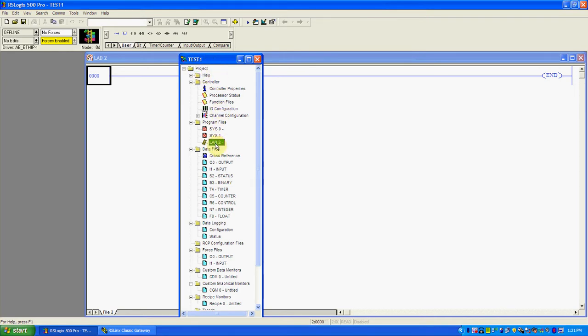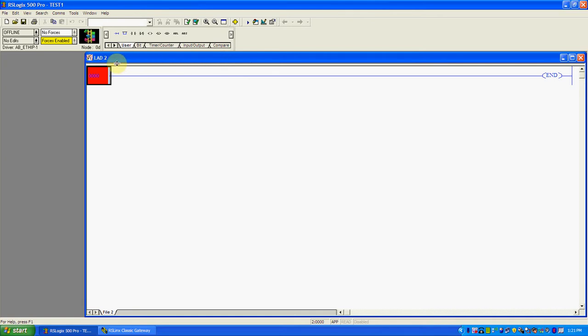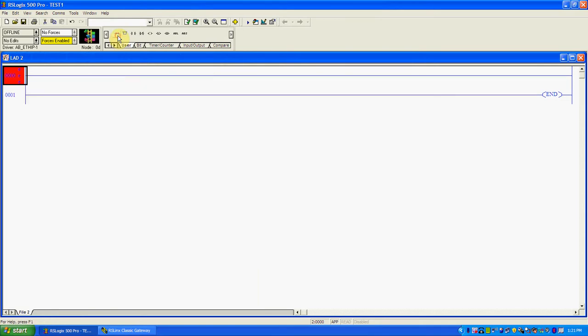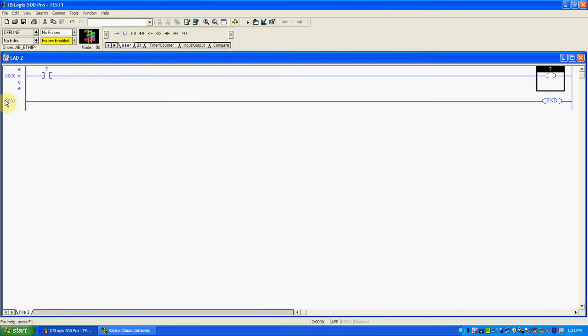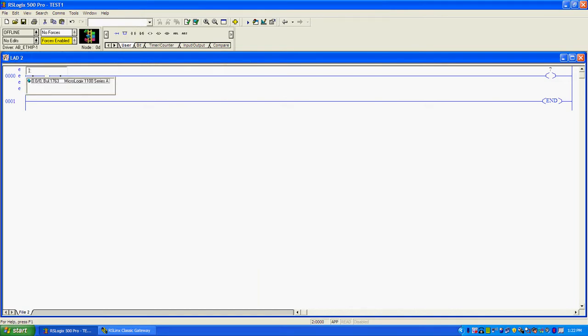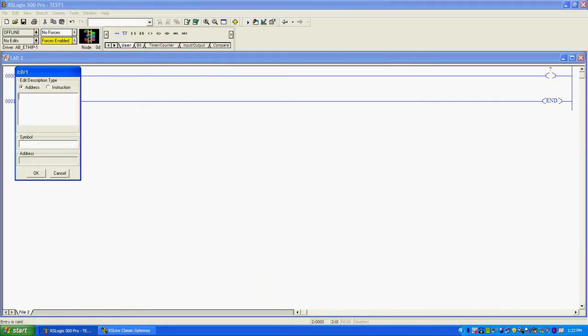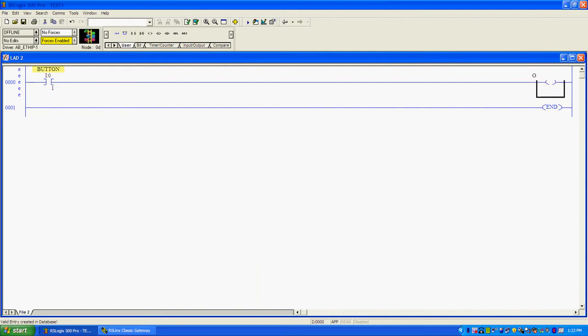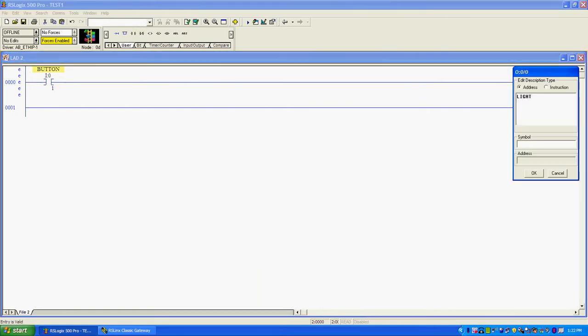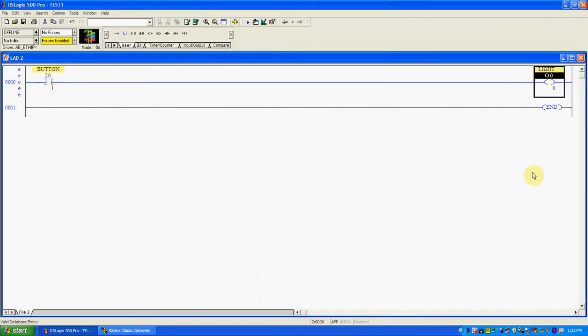If I have Ladder 2 open and click on it, this is the Ladder 2 I'm looking at. I'll expand it. In Ladder 2 you can add rungs, you can add contacts — it's really whatever you want. This contact is going to reference somewhere in those data files. I can choose what I want — I'm going to take input word 0, bit 1, and we'll call that a button. I'm going to turn on an output when the input's on, so I'll go O slash 0 — that's word 0, bit 0 of the outputs, and that might be a light. You should always comment everything as you go. What you're doing is assigning an address comment, so this address is always going to have this comment. Everywhere I use this address, we'll have the word 'light' associated with it.